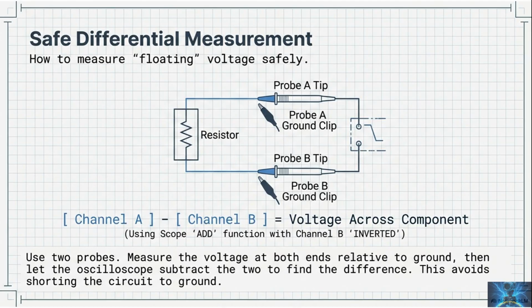Safe differential measurement. Sometimes you need the voltage across a component that isn't referenced to ground. A safer method is to use two channels. Measure each side relative to ground, then subtract one channel from the other using the scope's math functions. That gives the voltage across the component without moving the ground clip into a dangerous place. This is a big deal in power electronics and industrial troubleshooting.